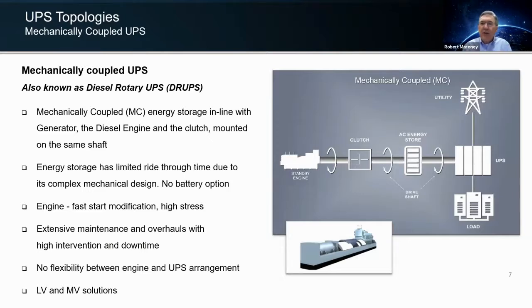What you've seen historically in the United States is when you get into more of what we call a train. You have essentially a standby generator, clutch connected to your energy storage device, then you go ahead and connect into the UPS. So it's a long, unified system. Generally very large capacity, you have to have a very, very fast start genset because those systems usually have just a few seconds of ride through time because they are physically connected.